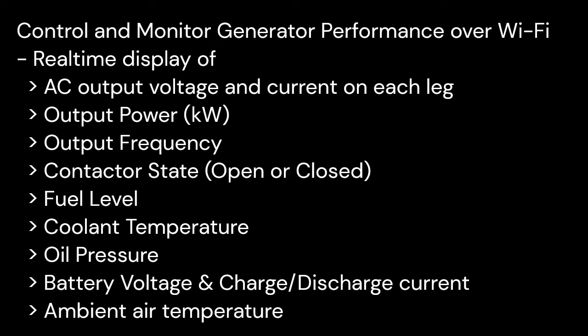Regardless of how the generator was started, you can monitor the generator's performance over Wi-Fi. The system provides real-time display of the AC output voltage and current on each leg, the total output power in kilowatts, the output frequency, the state of the contactor, the fuel level, the coolant temperature, the oil pressure, the battery voltage as well as battery charge or discharge current, and the ambient temperature.